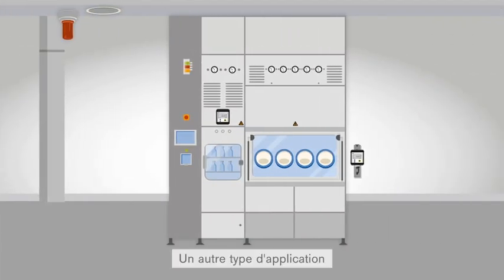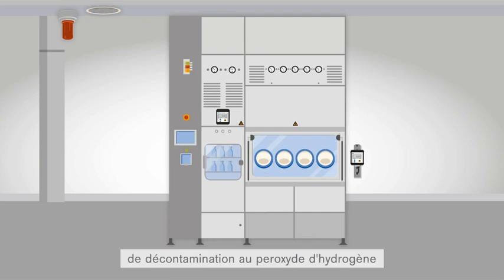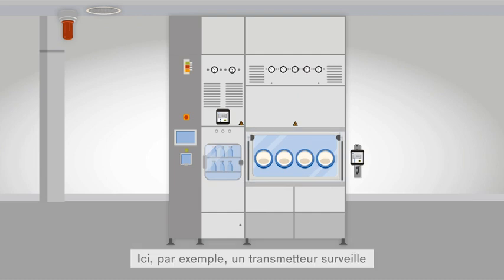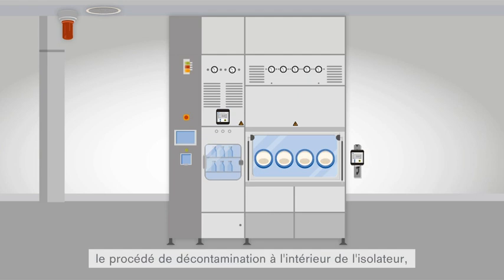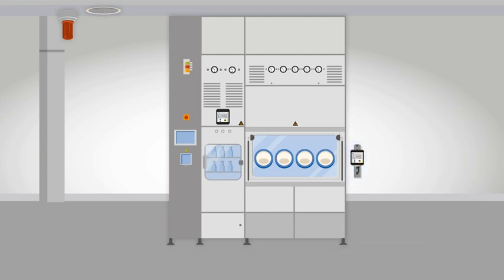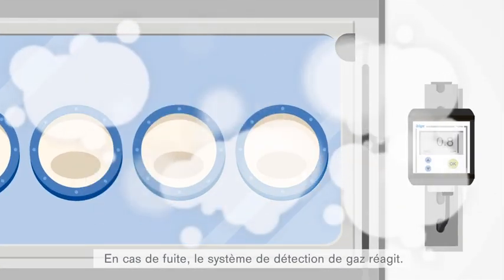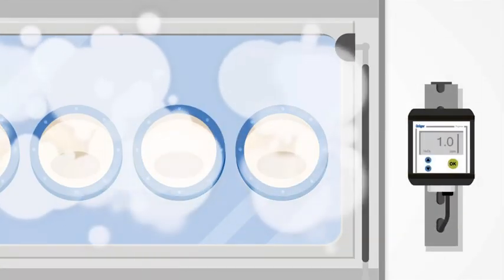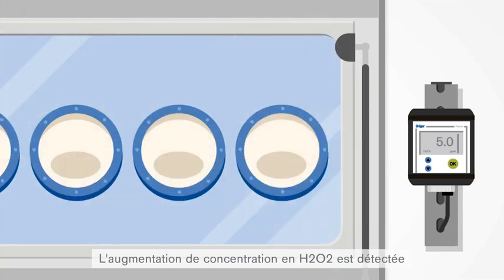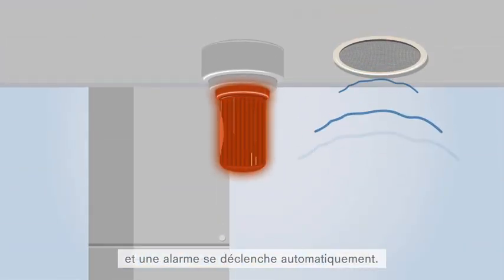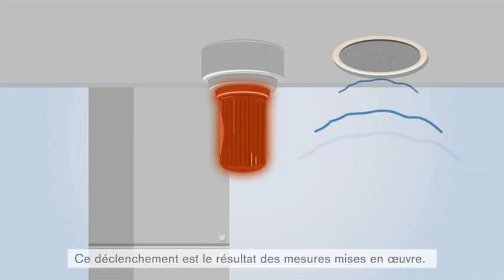A further application scenario for decontamination with hydrogen peroxide is the usage in isolators. Here, one transmitter monitors the decontamination process inside the isolator, while another is arranged adjacent to the isolator to detect leaks. If there is a leak, the gas detection system responds: the increasing H2O2 concentration is detected and an alarm is automatically triggered.